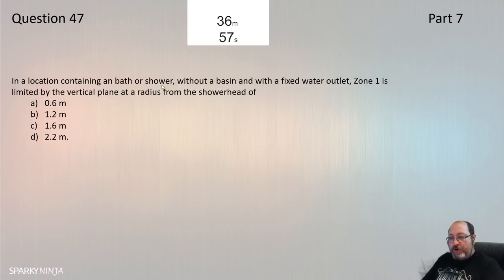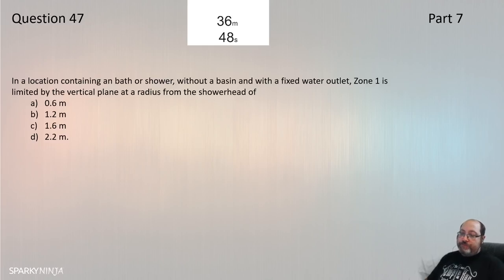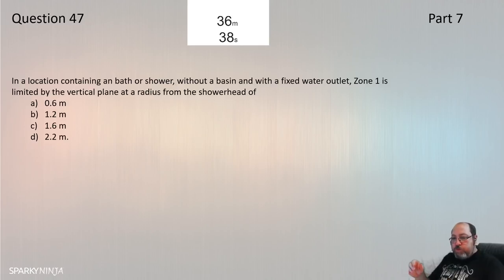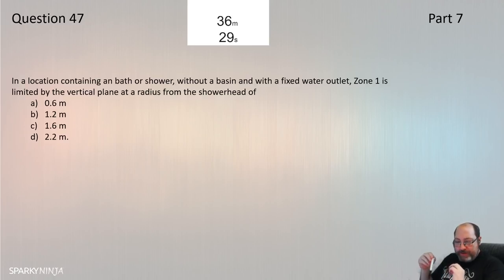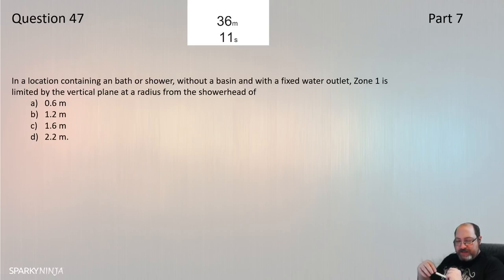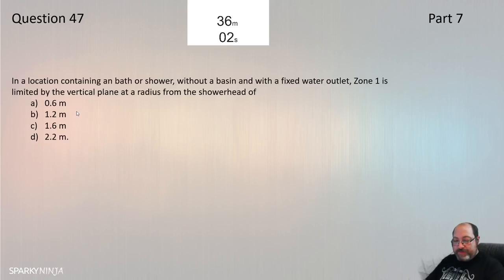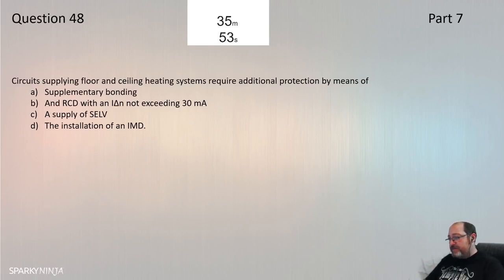Question 47: Bath or shower — regulation 701. This is about the scribing of zones. Zone 1 is limited by the vertical plane at a radius from the shower head; the distance from the centre point of the fixed outlet is 1.2 metres. Question 47 is B, from 701.32.3.